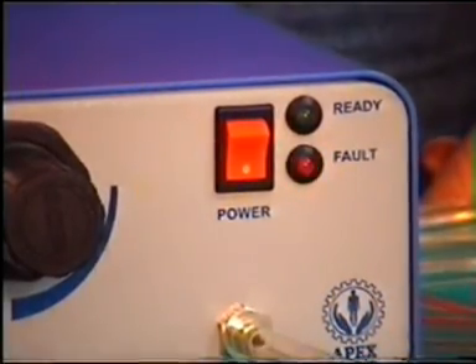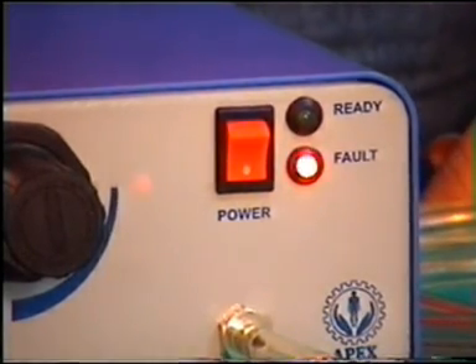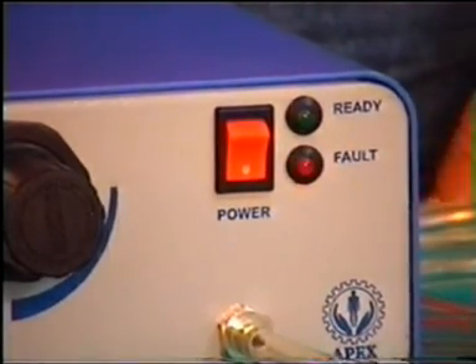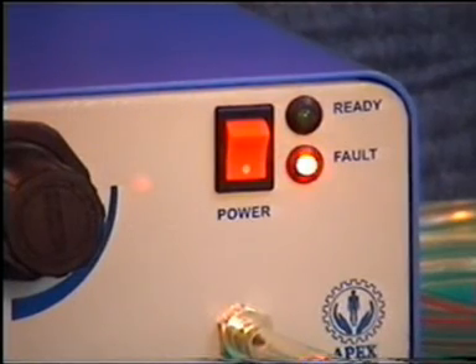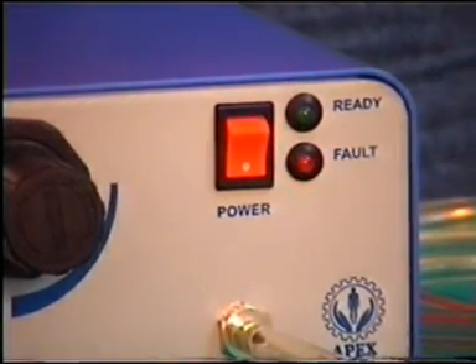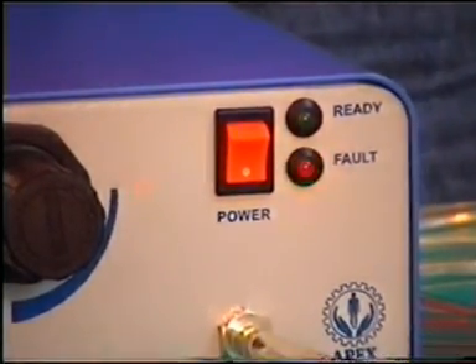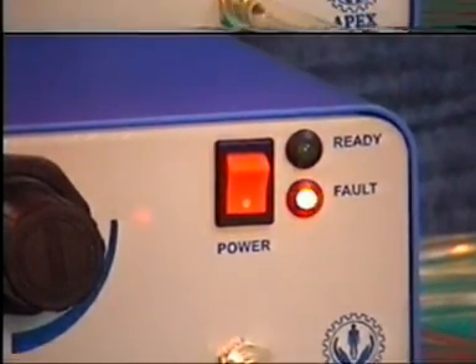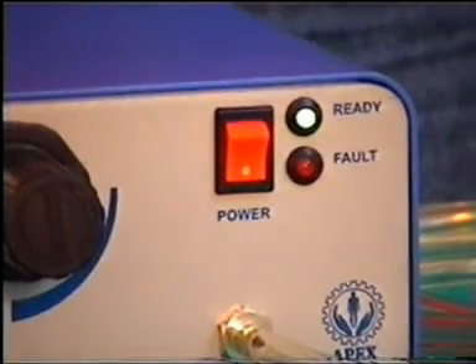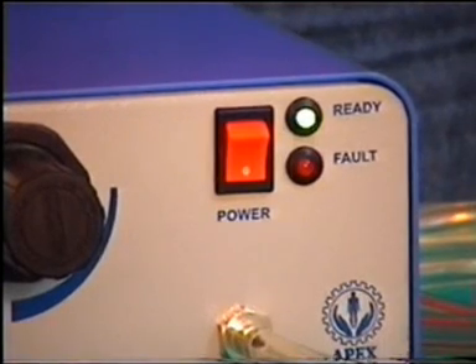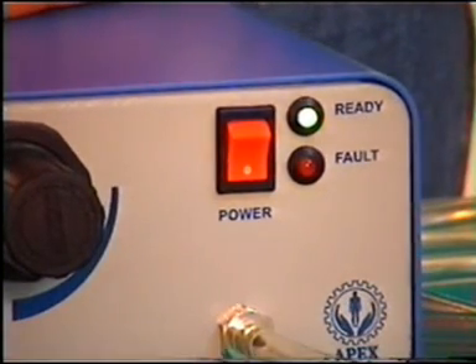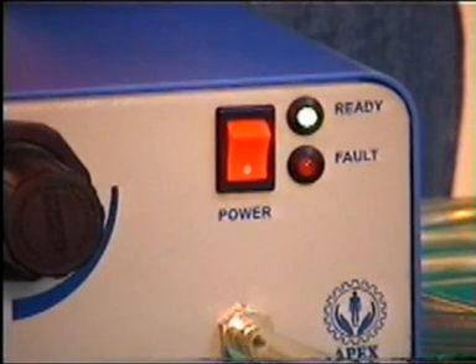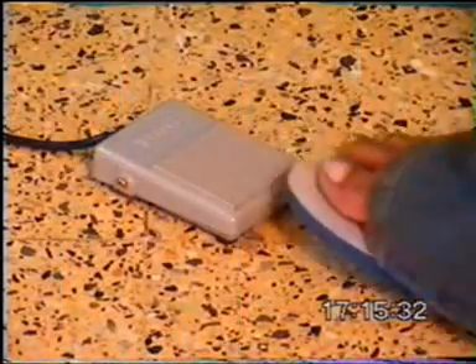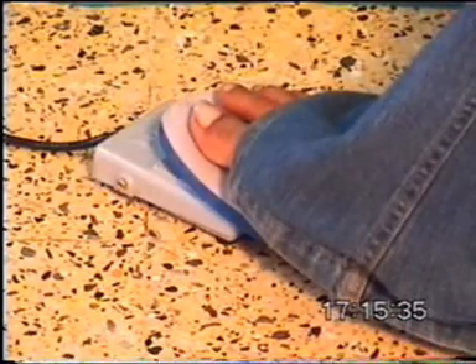The red LED indicator flashes if the foot switch is electrically short-circuited. To prevent any accidental operation, the system will not function if the foot switch is short. The system will start functioning the moment the foot switch is replaced. The flashing green LED indicator indicates that the system is now running the self-test. Every time the system is switched on, the controller inside will run the self-test to check functioning of the electro-pneumatic system. The LITHOSPLIT system is now ready to be activated using the foot switch.